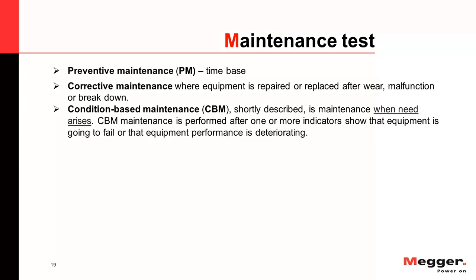If a problem occurs between maintenance cycles, that is corrective maintenance — correction of a failure. There is also condition-based maintenance (CBM), which is very good for numerical protection relays. CBM involves performing a fast test and checking for any indication of an issue. If there is no indication, you do not need to take an outage, which helps your KPI. All approaches work well — it depends on the utility and what they need. All these tests are performed using Megger test equipment such as the Freja and SMRT series.